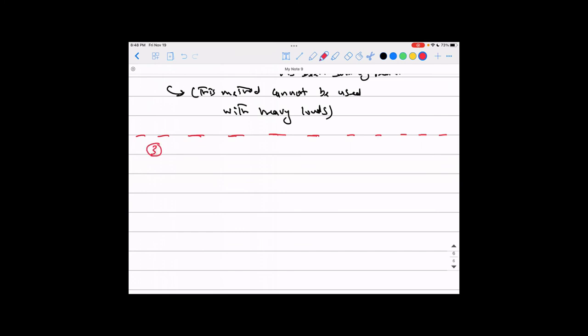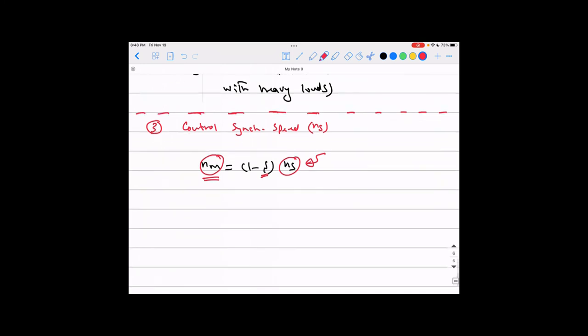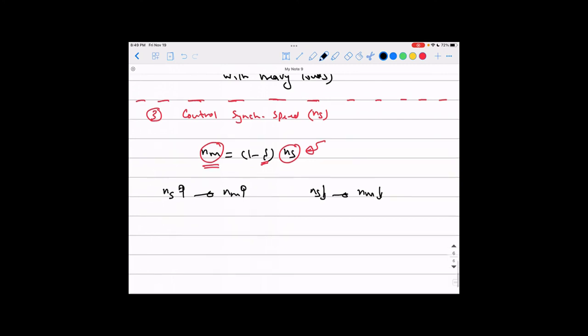Method three: control the synchronous speed. The mechanical speed equals (1 - s) × ns. So if you keep the slip constant, any change in synchronous speed directly changes the mechanical speed — and that is what we want. If the synchronous speed goes up, the mechanical speed goes up; if synchronous speed goes down, the mechanical speed goes down. Unlike the previous two methods where we could only reduce speed, now we can even increase it.